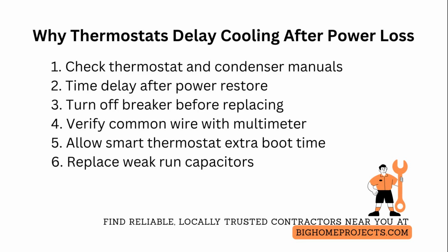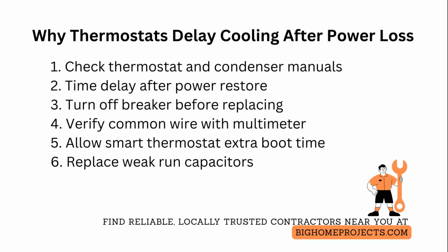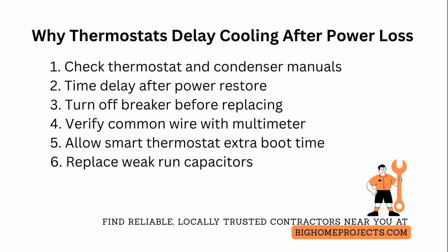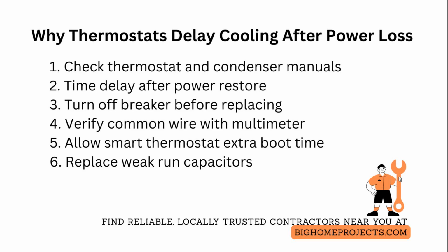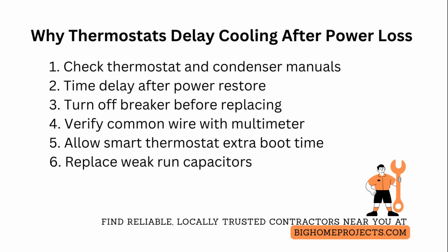To speed recovery after a power loss, ensure the outdoor unit contactor and capacitor are in good condition, replace weak run capacitors which can prevent proper start, and use a surge protector on the furnace or control board to avoid corrupted startup states. For properties with frequent outages, consider a small uninterruptible power supply sized for the thermostat to maintain settings and shorten the user-facing wait, keeping in mind the compressor protective delay will still apply at the condenser.